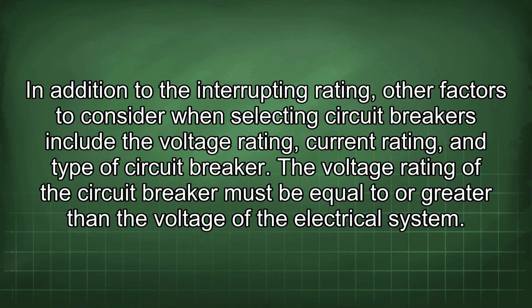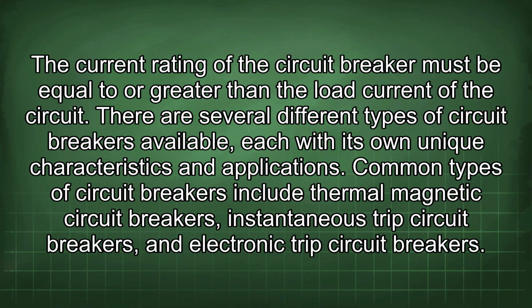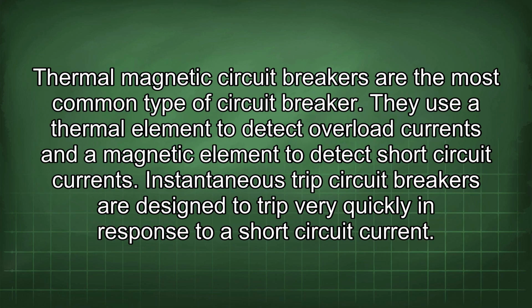The voltage rating of the circuit breaker must be equal to or greater than the voltage of the electrical system. The current rating of the circuit breaker must be equal to or greater than the load current of the circuit. There are several different types of circuit breakers available, each with its own unique characteristics and applications. Common types of circuit breakers include thermal-magnetic circuit breakers, instantaneous trip circuit breakers, and electronic trip circuit breakers. Thermal-magnetic circuit breakers are the most common type of circuit breaker. They use a thermal element to detect overload currents and a magnetic element to detect short-circuit currents.